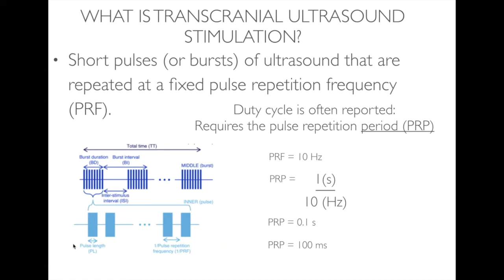To calculate the duty cycle, one way requires the pulse repetition period. That involves taking the pulse repetition frequency, which in this example is 10 hertz. Each of these pulses along the bottom will be delivered at a frequency of 10 hertz. To get a pulse repetition period, you just divide 1 by the frequency, which is 10 in hertz, to give you 0.1 seconds, or converted into milliseconds, 100 milliseconds. So the pulse repetition frequency is 10 hertz and the pulse repetition period is 100 milliseconds, meaning the interval between each pulse is 100 milliseconds.